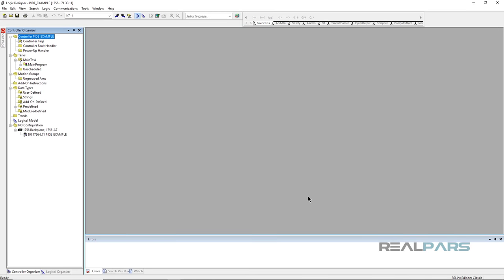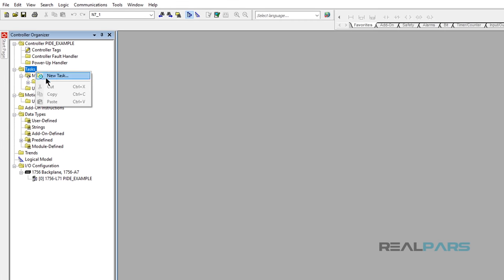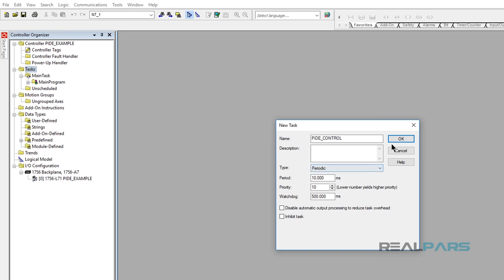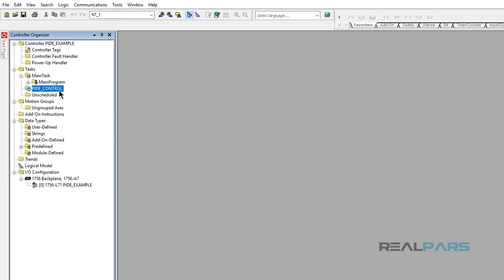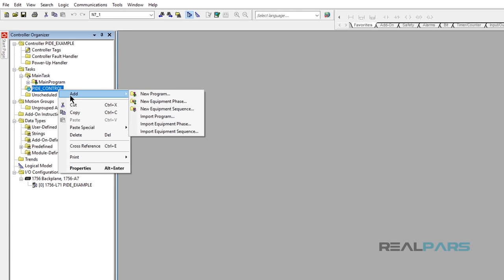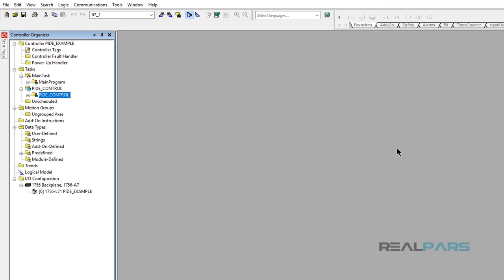For the next step, we need to create a new routine by making a new task and a new program. I'll create a new scheduled task by right-clicking on Tasks and then clicking New Task. In the next window, I will enter PIDE Control as the name for the task. The period of the task automatically becomes the sample rate of the PID loop, so it is best to set it up in its own periodic task. I'll leave these settings without changes and continue to create a new program by right-clicking on the PID Control task. I'll open the Add menu and click New Program, naming it PID Control, then click OK.